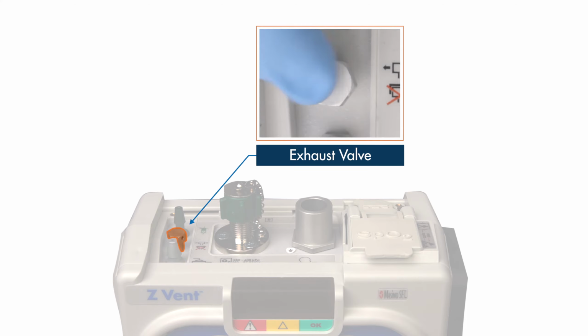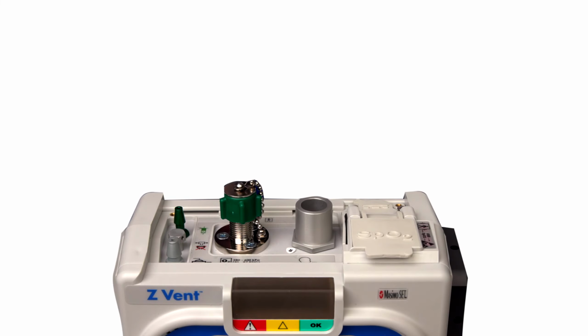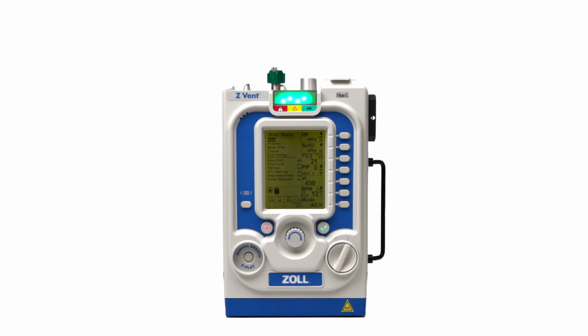Between the 2 nozzles, the hexagon-shaped part is the backup exhaust valve for the green and silver lines. The exhaust valve prevents excess pressure from building up inside the transducer and exhalation lines. Now we will look at the front panel of the device.